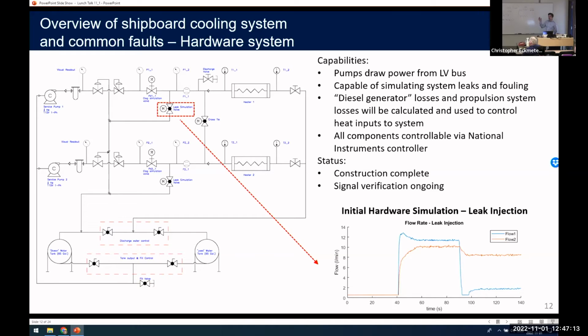Based on however much the electrical generator is loaded, the efficiency multiplied by the efficiency of the generator and a constant factor for the waste heat loss through the cooling jackets, we then place a load into the heating system. So based on how much electrical power you're using, you need more power, and there's more waste heat you have to dissipate with the cooling system. This way we can review the coupled dynamics. You might have a fault or failure in the cooling system that affects the cooling system flow. Maybe it affects the amount of waste heat you're able to dissipate, and it's going to cause a thermal runaway, or maybe it's just going to cause a slightly greater heat rise over the emulated cooled engine.